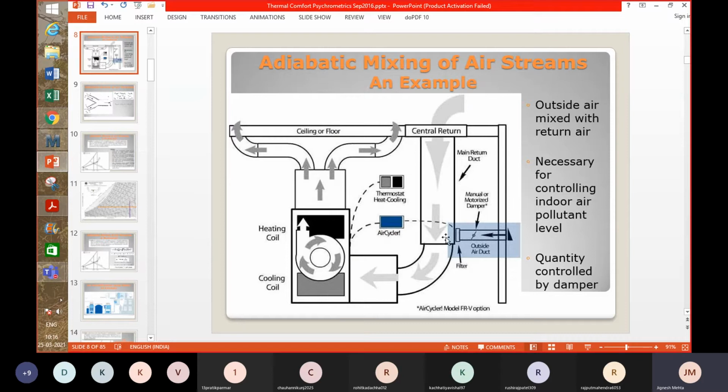If you don't bring the outside air, like in the case of split AC, what you presume is that you have loosely built buildings, so there are gaps through which the outside air is coming, or you are opening and closing the door frequently, so the outside air is coming from that also, right? It's generally not advisable to remain inside a conditioned space without any outside air, because there could be pollution generation inside the space. And this is just one type of pollution generation I am mentioning.